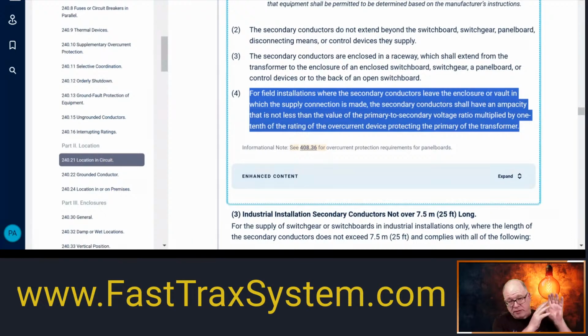So whatever the primary protection is, you take 1/10 of that, and you take the ratio, again, 2.31. We got that by taking 480 and dividing it by 208. That's where we get this voltage ratio. We multiply that by 1/10 of the amp rating of the primary protection, and that determines the minimum size of the secondary conductors. But again, chances are it's going to be much larger than that. So usually item 4 doesn't come into play. Now, let's look real quick at an example.